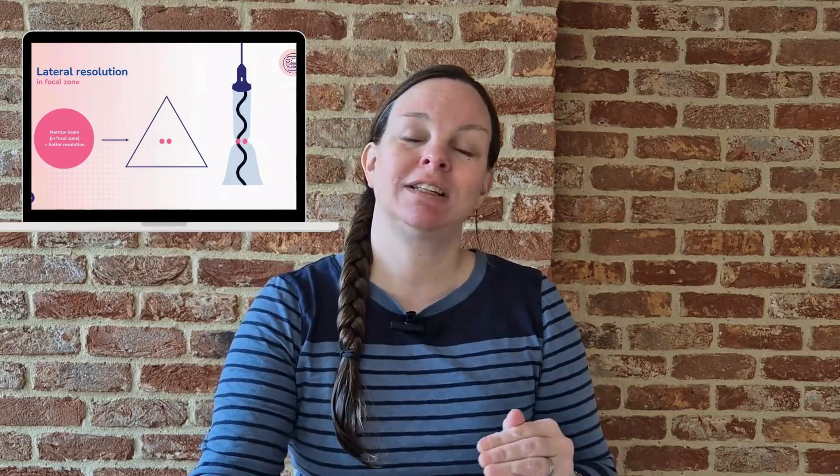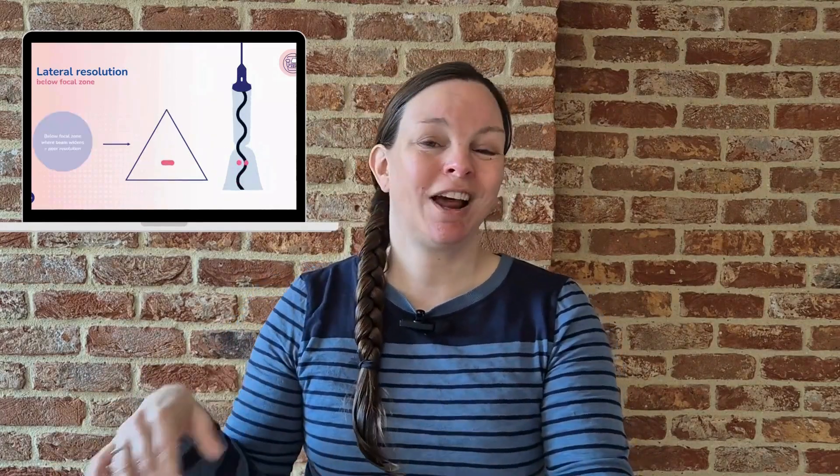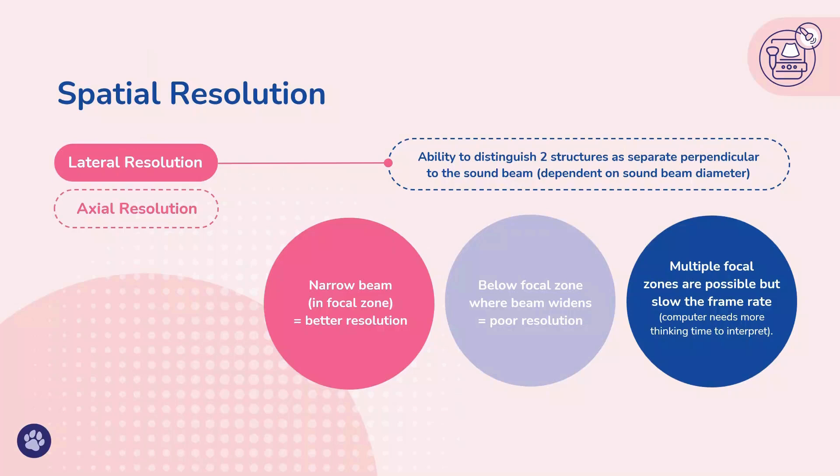The focal zone is where your lateral resolution is best — that means how well the machine can tell apart two structures that sit next to each other side by side at the same depth. But if the focal zone is too shallow or too deep, you're using a wider part of the beam and you lose that sharpness.